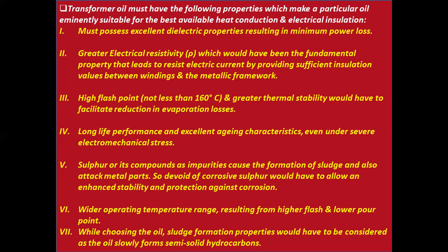Number five, sulfur or its compounds as impurities cause the formation of sludge and also attack metal parts. So being devoid of corrosive sulfur allows enhanced stability and protection against corrosion. Number six, wider operating temperature range resulting from higher flash point and lower pour point. Seven, while choosing the oil, sludge formation properties have to be considered, as the oil slowly forms semi-solid hydrocarbons.